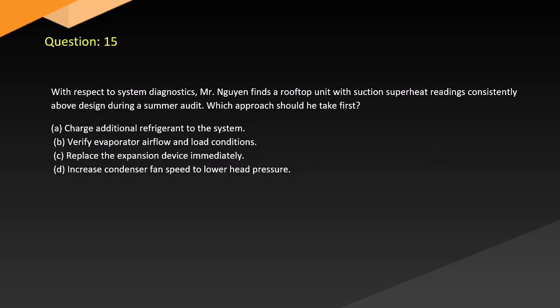Question 15. With respect to system diagnostics, Mr. Nguyen finds a rooftop unit with suction superheat readings consistently above design during a summer audit. Which approach should he take first? A. Charge additional refrigerant to the system. B. Verify evaporator airflow and load conditions. C. Replace the expansion device immediately. D. Increase condenser fan speed to lower head pressure.